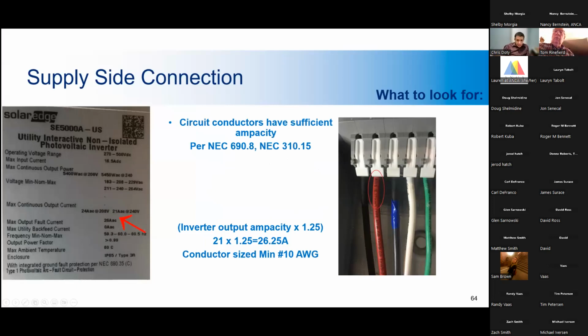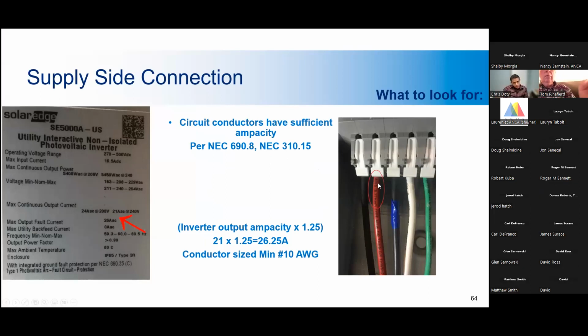With the supply side connection as well, you have to ensure that the conductors are sized appropriately, and you do that by checking the labeling on the wires themselves. You look at the inverter nameplate for the max continuous inverter output current right here. You multiply that by the 125% of the continuous load, and then you verify the labeling on the conductor to make sure that it can hold that amount of amperage.